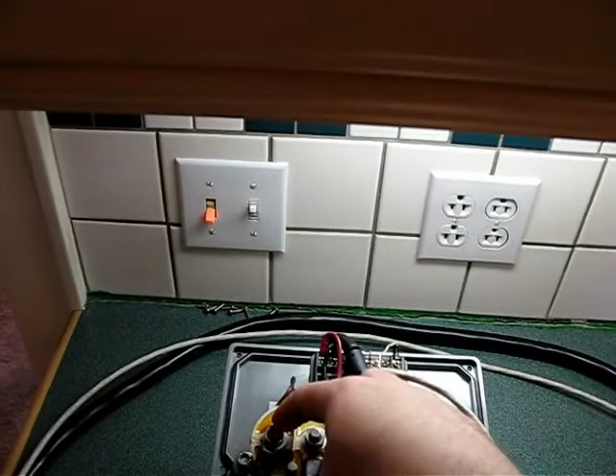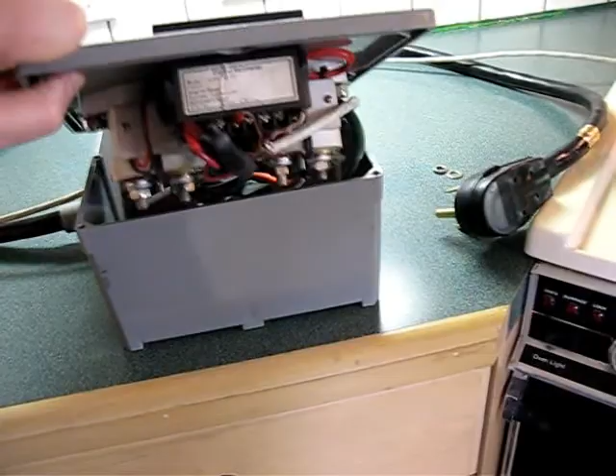Well, that's all well and good. However, this particular unit was mounted in my car upside down, about like so, and it was shaking all the time as I trundled down the road. So over the course of a year, my new theory is that this actually weakened that connection, or backed off the nut just so slightly, causing it to not make a good solid contact between this cable's lug and the contactor, which is bad and causes heat. So I'm guessing it caused enough heat that it melted the insulation around the cable, and possibly was so much heat on the terminal itself that it caused this discoloration.